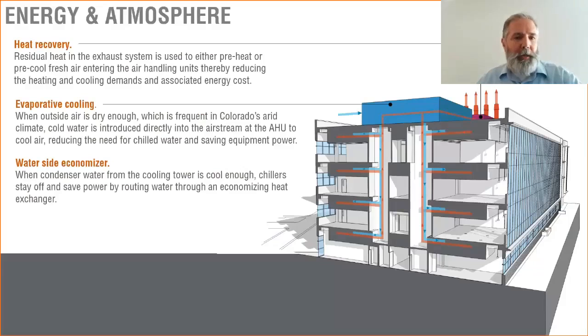In addition to the chillers on the building, we also have an evaporative cooling system, which is essentially a really fancy swamp cooler that introduces atomized water directly into the airstream, thereby pre-cooling the air. And then we also have a water side economizer, which, in addition to the chillers, is a way to use that cold water by introducing it into the economizing heat exchanger. Thereby you can turn off the chillers and save energy.